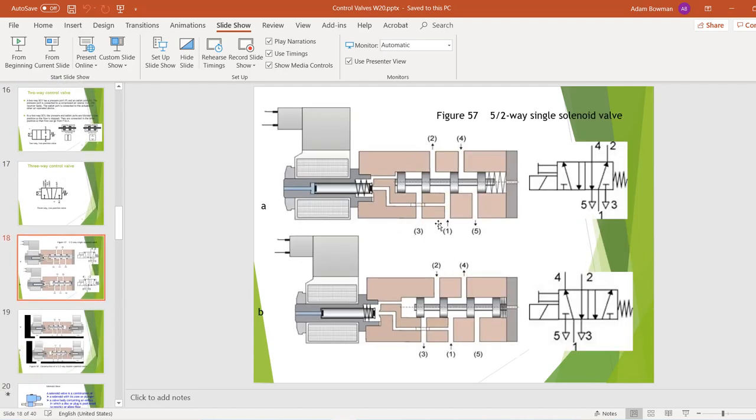This kind of shows a little bit better 3D model showing what's actually happening inside the valve itself. So this is the valve that's shifting back and forth. So air pressure is coming up here, going to the left air line. The right air line is going to exhaust out. Then when this is shifted over, the air goes to the right and the left is exhausted out. So on the left here, this is the solenoid. That's causing this to push over. When this is not activated, this is retracted the other side by the spring.